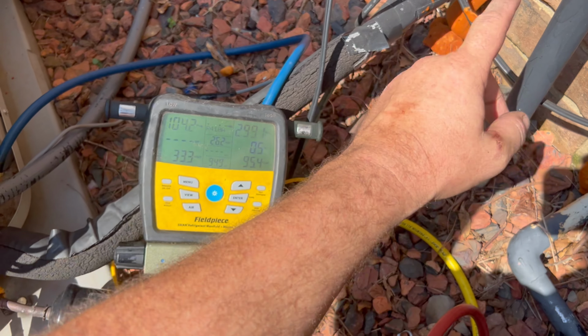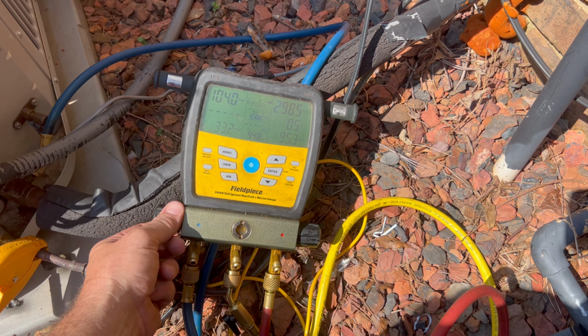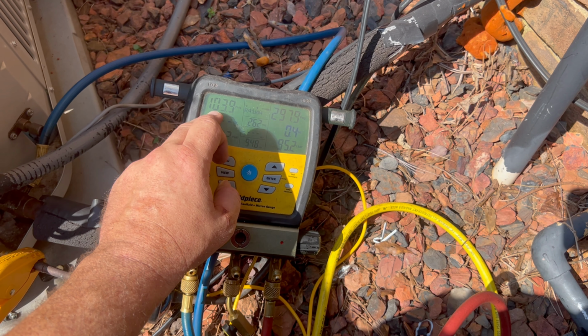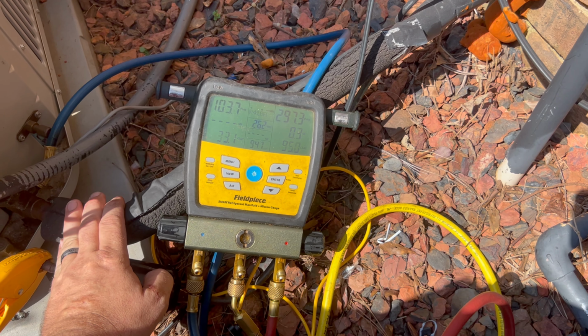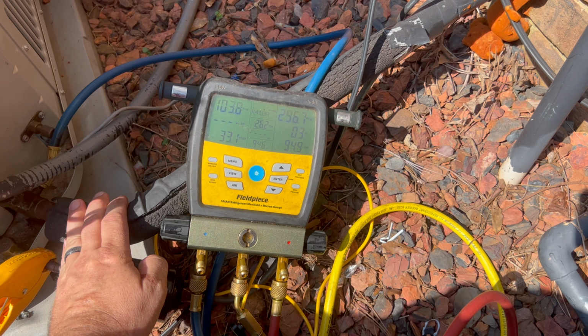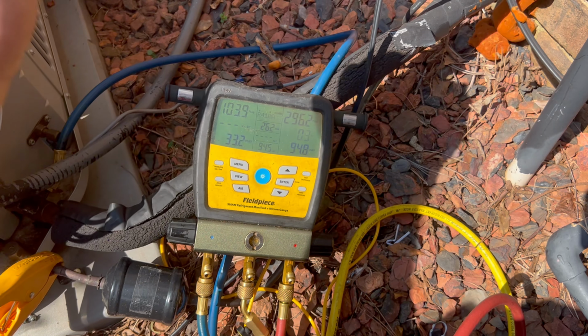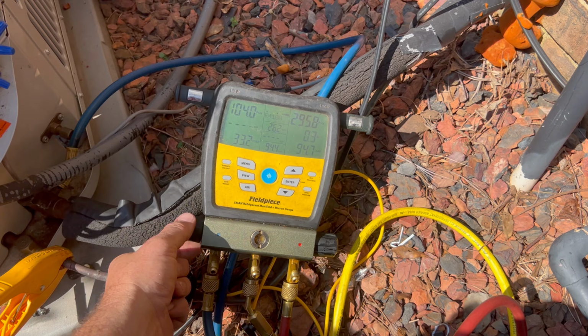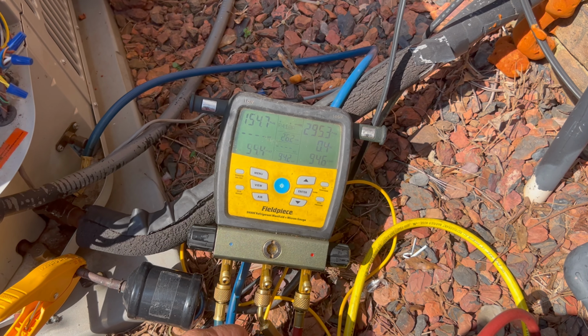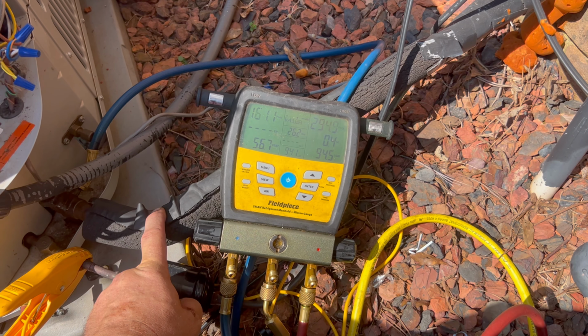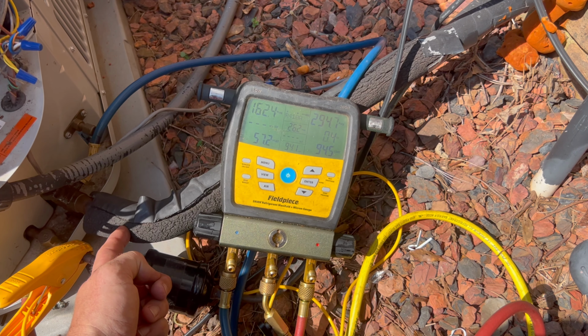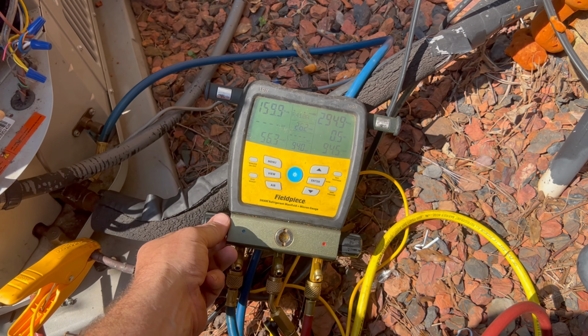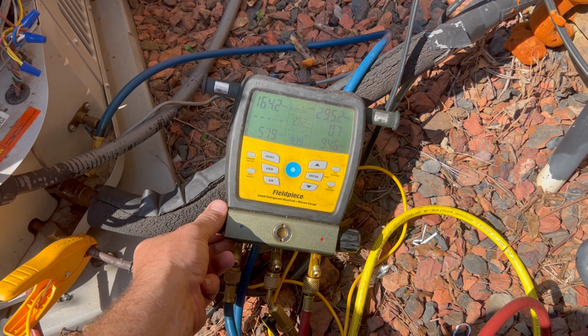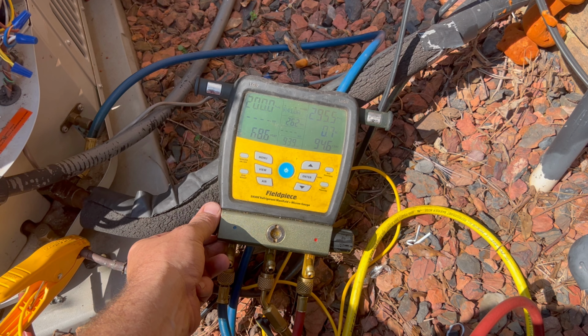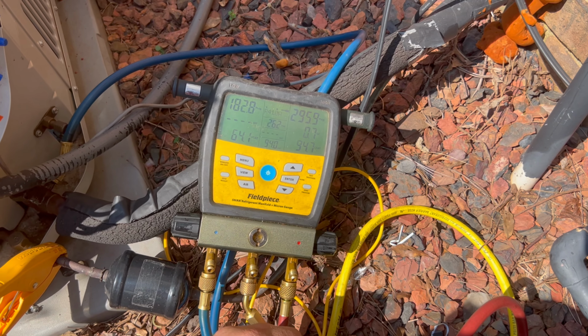But in this particular case, we do have an expansion valve on the inside. So you have to remember, every time we add a little refrigerant, that expansion valve is equalizing with this pressure, taking our essential superheat measurement with a bulb on the line, and it's pressing down on a diaphragm against a spring, opening that valve and letting as much through as possible. When we open up our line here to add a little refrigerant, we're increasing the pressure on this, which is dropping the temperature on our line. So that valve is going to want to start closing down because it says, whoa, wait a minute, something's way wrong. We got too much pressure, too low temperature. So it is kind of a seesaw procedure, because every time you add a little bit to it, it's going to take a second for it to readjust and figure itself back out.